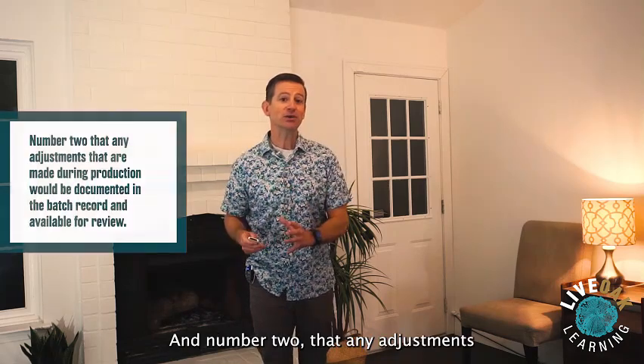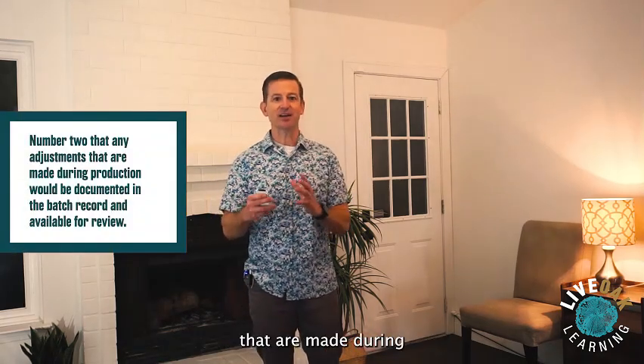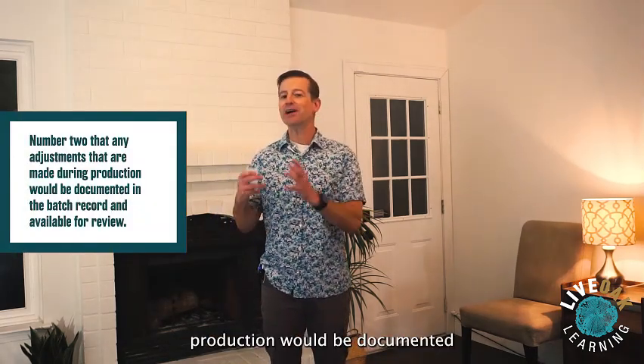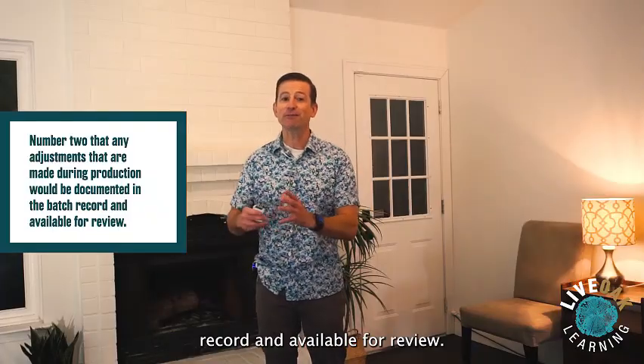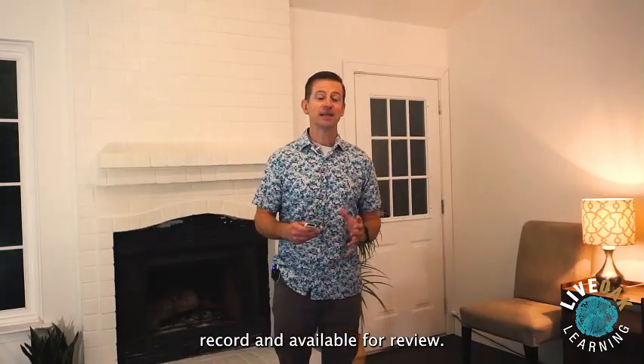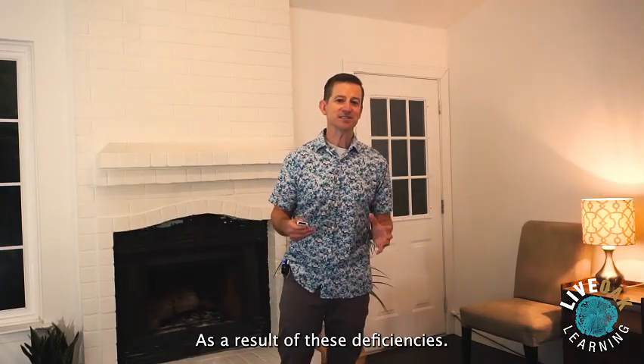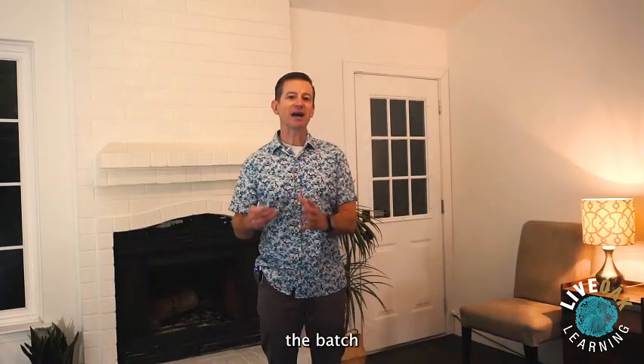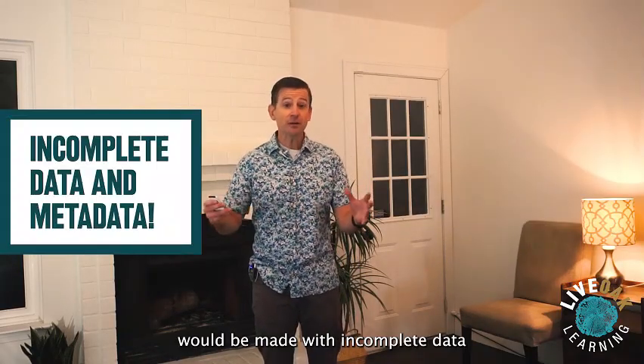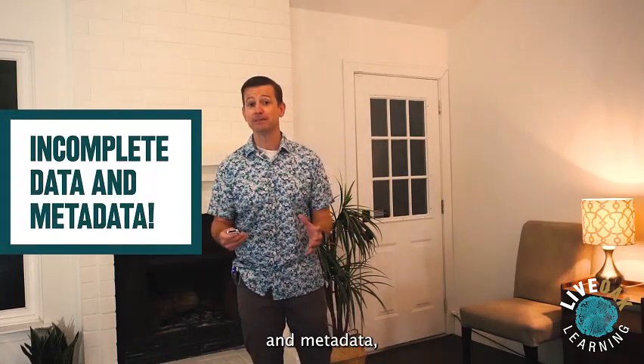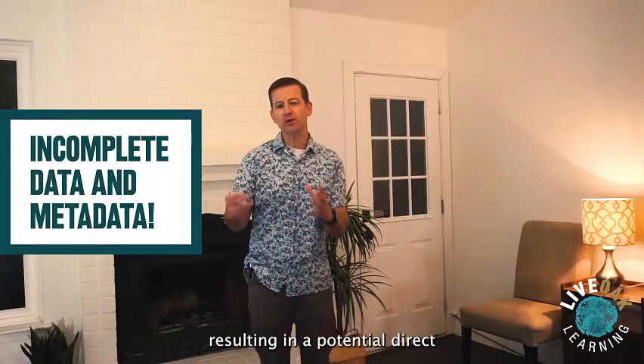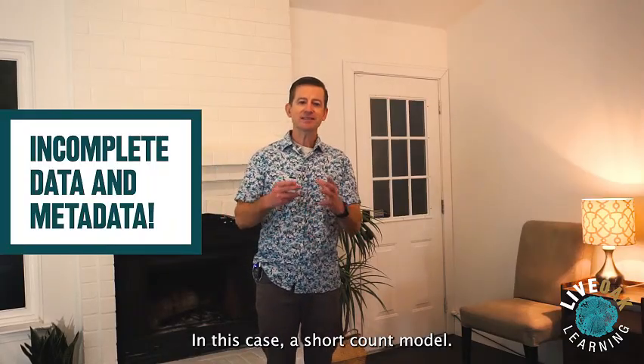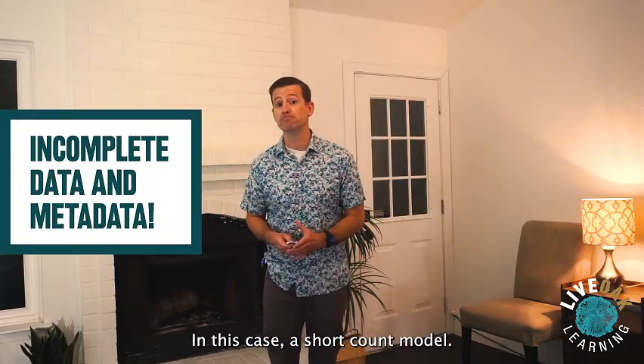And number two, that any adjustments that are made during production would be documented in the batch record and available for review. As a result of these deficiencies, the decision to release the batch would be made with incomplete data and metadata, resulting in a potential direct patient impact, in this case, a short count bottle.